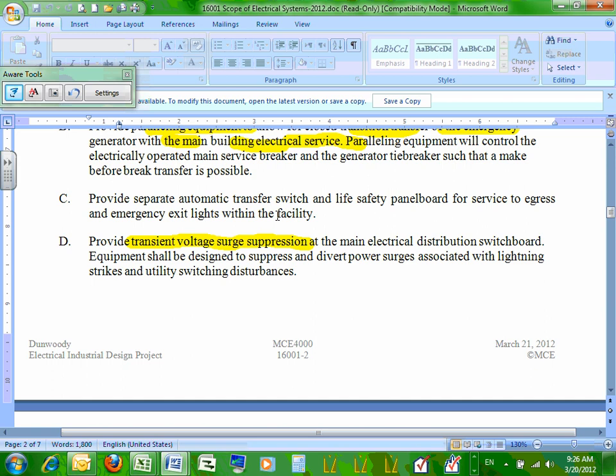Either way, the busing in the switchboard, I want to minimize my distance to my phase, neutral, and ground for my TVSS. I kind of like it in the board, but we still usually want a breaker oftentimes to feed that TVSS. Sometimes it's built into the TVSS, sometimes it's a breaker in the board. I don't think I said in or out, but I'll leave it to your choice on that one. If it's in the board, it literally gets built with the switchboard, makes for clean. If it's not on the board, then you might mount it on top to keep these leads short, because the longer these leads are, the less effective the performance of the transient voltage surge suppression. So we really want to keep those leads as short as possible.